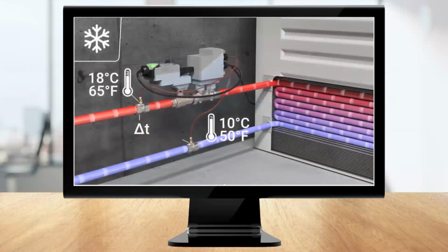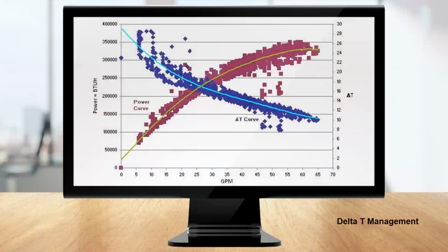But as you see here, there are 2 temperature sensors that are included. The low delta T is an indicator of inefficient heat transfer. Delta T manager will hold a delta T low limit threshold and force that coil to maintain that higher delta T while still achieving the load to the space, provided the delta T set point is properly installed.